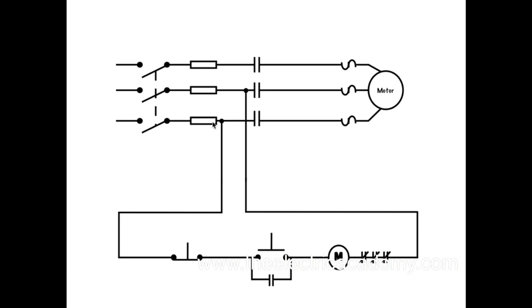Here's full voltage control. Let's say this is like 120-120-120, and this control circuit down here is going to be 208 volts - pretty standard. You'd have this coming between these two lines, you have 208 volts. The thing you have to make sure is that this coil can handle 208 volts, which is possible.